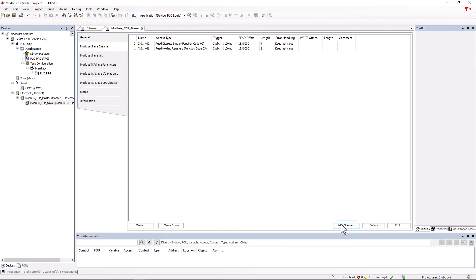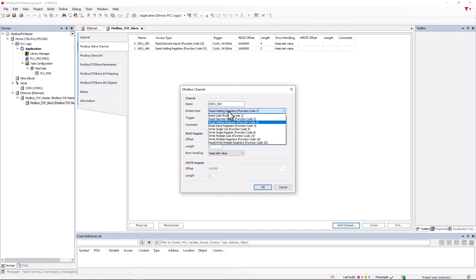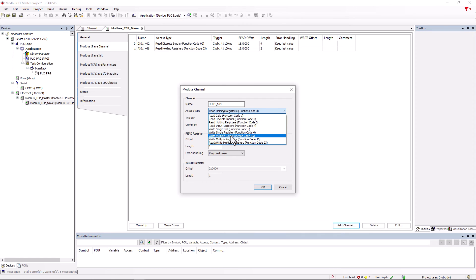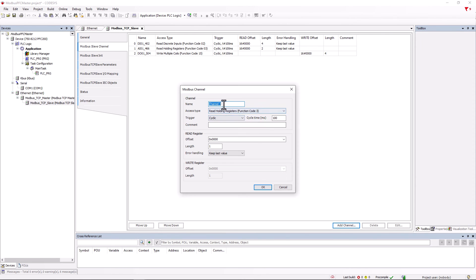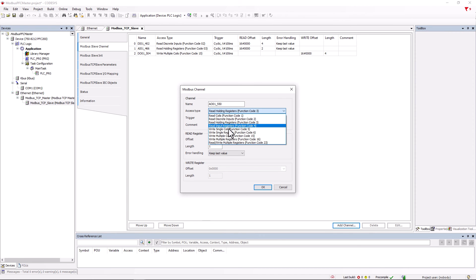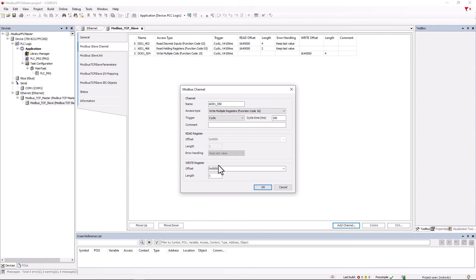In this way, we also create the outputs. First, the digital outputs with function code 15 write multiple coils with length 4 and the analog outputs with function code 16 write multiple registers and length 2.